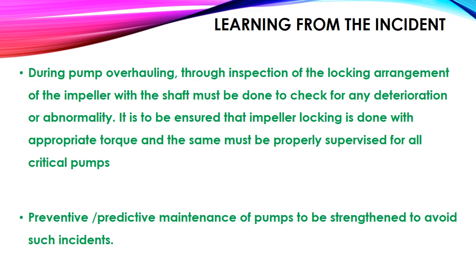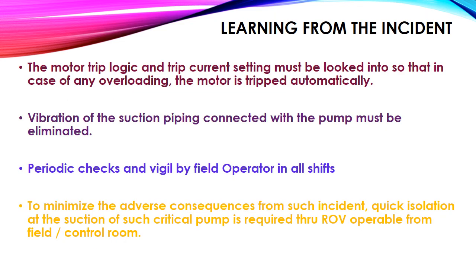Learning from this incident, during pump overhauling, thorough inspection of the locking arrangement of the impeller with the shaft must be done to check for any deterioration or abnormality. It is to be ensured that impeller locking is done with appropriate torque, and the same must be properly supervised for all critical pumps. Preventive or predictive maintenance of pumps is to be strengthened to avoid such incidents. The motor trip logic and trip current setting must be looked into so that in case of any overloading, the motor is tripped automatically. Vibration of the suction piping connected with the pump must be eliminated. Periodic checks and vigil by the field operator in all shifts.